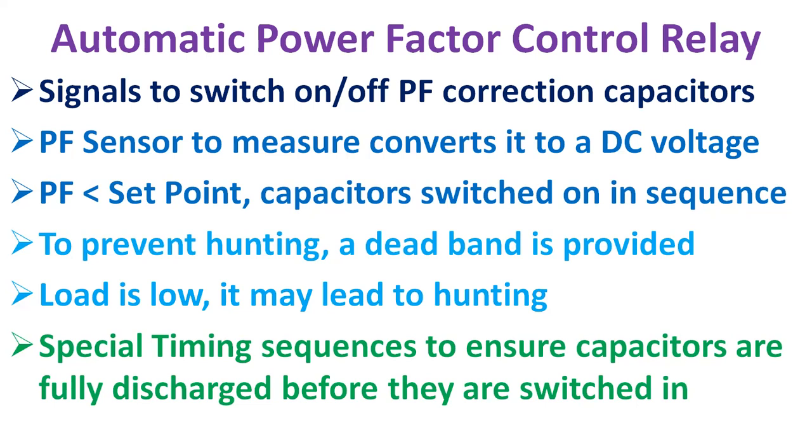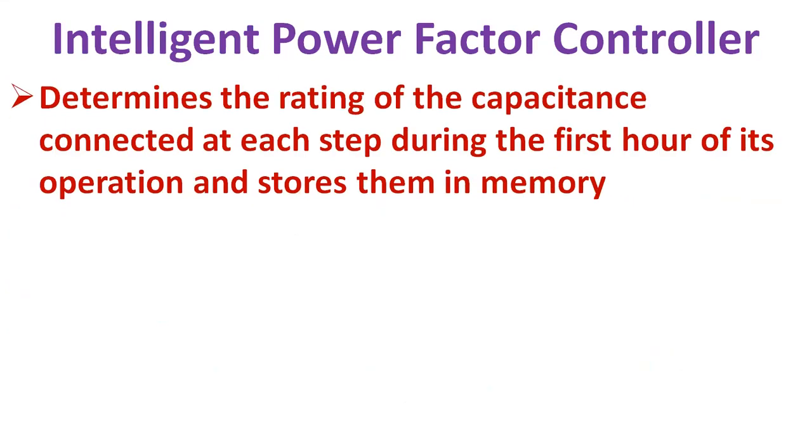This avoids a dangerous overvoltage transient. The solid state indicating lamps display various functions that the operator should know and also indicate each capacitor switching stage. Then we have the intelligent power factor controller, IPFC.